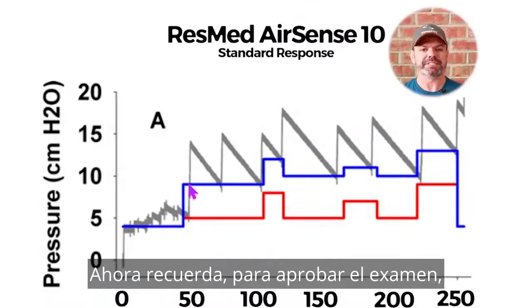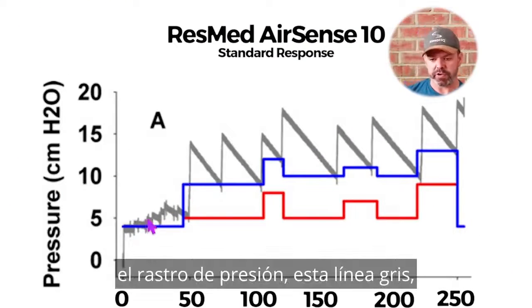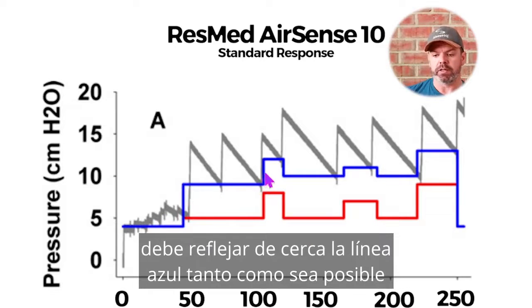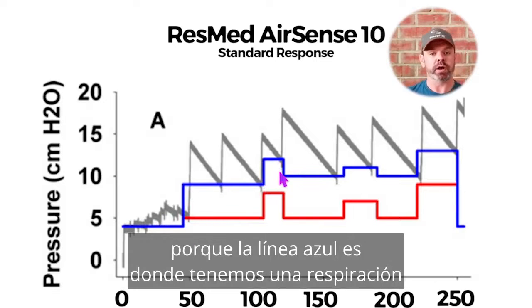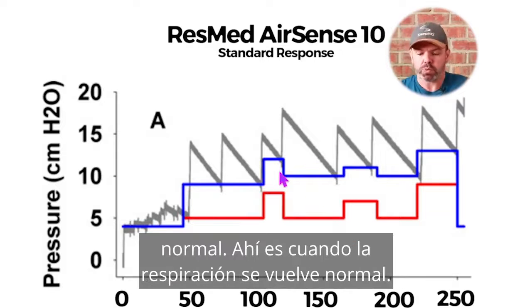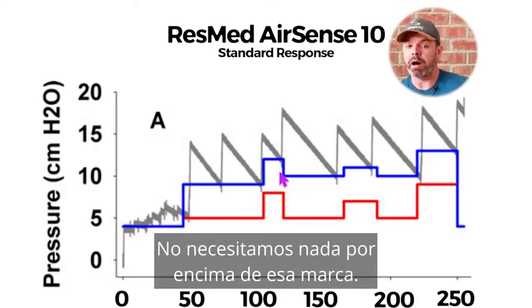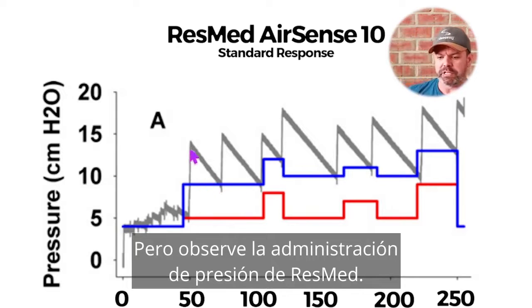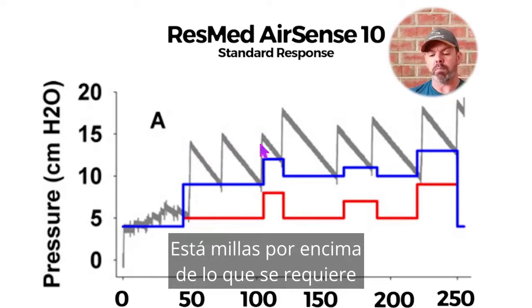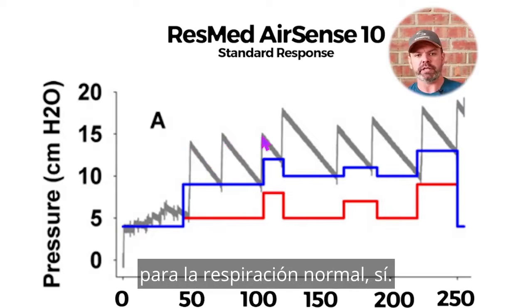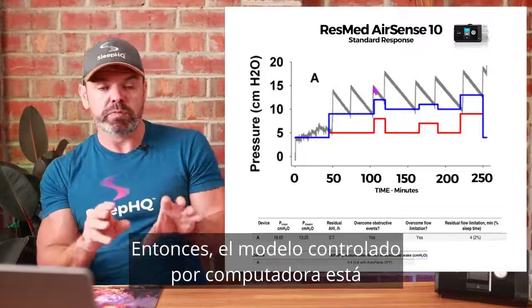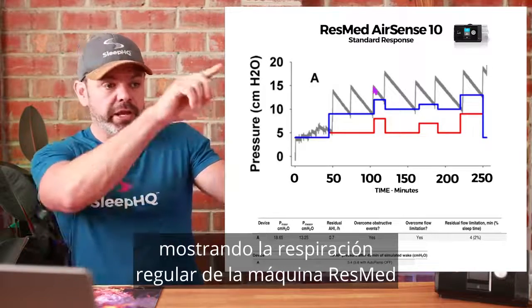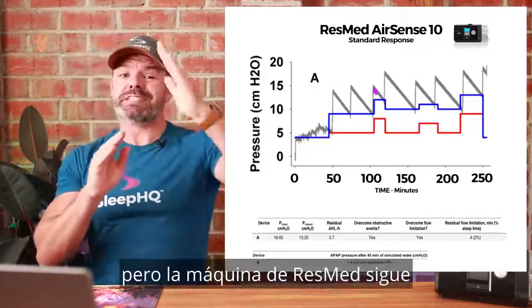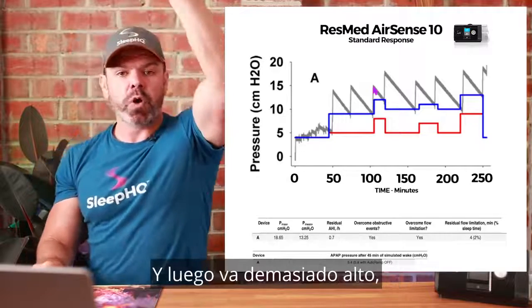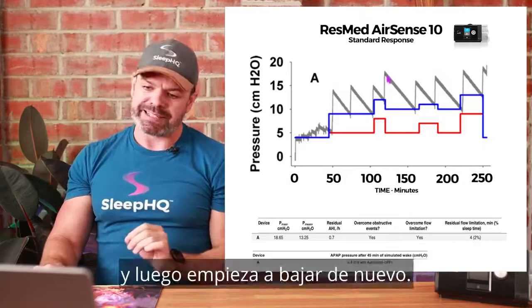Now remember, to ace the exam, the pressure trace, this gray line, should closely mirror the blue line as much as possible because the blue line is where we have normal breathing. That's when breathing becomes normal. We don't need anything above that mark. But look at the ResMed pressure delivery. It's miles above what is required for normal breathing. Yeah? So the computer-driven model is showing the ResMed machine regular breathing, but the ResMed machine is still going up, up, up, up, up, up. And then it goes too high, it realizes it's gone too high, and then it starts to come down again. It looks like the Himalayas here.